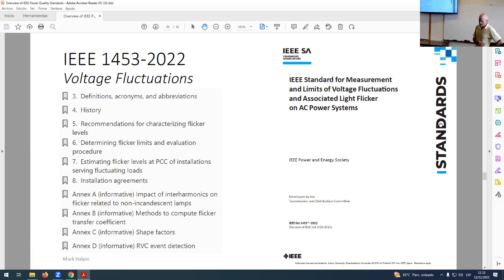So in the late 90s and early 2000s, we did a couple of things in IEEE. The first thing we did is we adopted outright the IEC flicker meter. Once we had something we could measure and quantify voltage fluctuations in terms of light flicker, then we needed some utility management practices. So we turned next and adopted outright IEC technical report 61000-3-7, which prescribes the limiting process for voltage fluctuations in flicker.